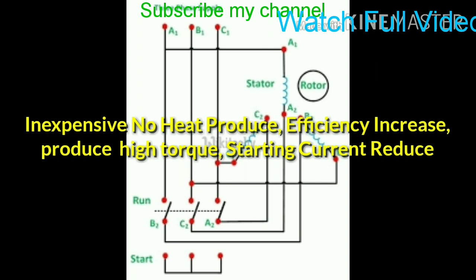Here are the advantages of star-delta starter: they are very inexpensive, no heat is produced on the tap changing device which increases efficiency, the starting current is reduced to one-third of direct-on-line, and they produce high torque per ampere of line current.